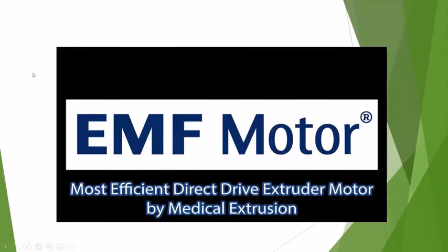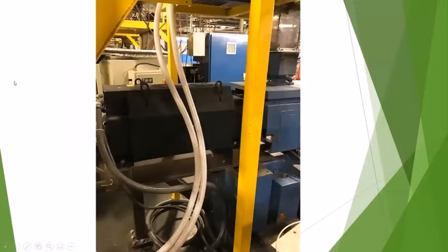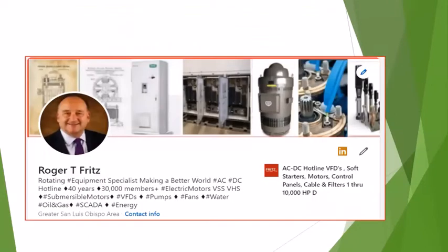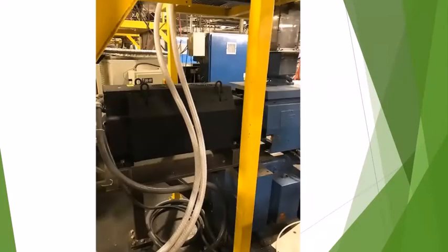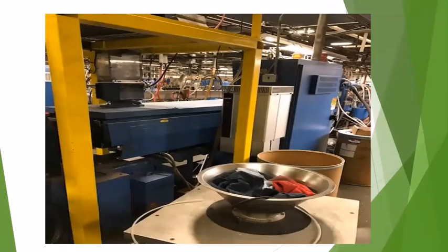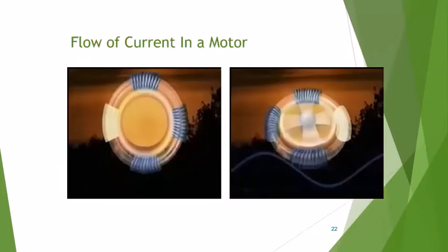We have to have the data of the gearbox. If we're going to be taking the gearbox out, we have to have the data of that gearbox so that we can properly calculate the torque and power. Because when we're trying to do it without gearing, we have to make sure we have the exact torque requirements, especially when you get into a PVC machine.